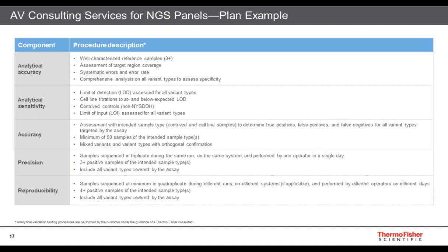We then segue into analytical sensitivity — assessing your limit of detection for all variant types. You'd also want to do a limit of input study. For limit of detection, we typically use cell lines diluted in a background of normal DNA/RNA to target a variant allele frequency, copy number, or fusion reads depending on what the assay is designed to detect. Contrived controls can also be used — pre-diluted to target allele frequency, copy number, or fusion read counts — though New York State does not recommend contrived controls.